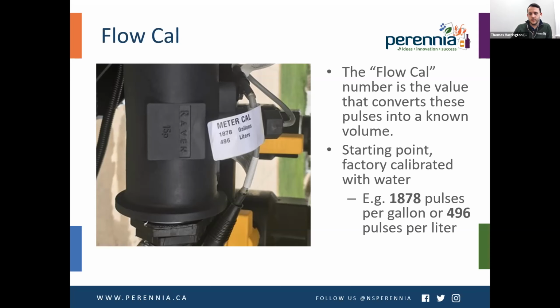What might cause this number to change is if you've got a solution with a slightly different density, or if your flow meter starts to accumulate a little bit of debris, or if it gets maybe worn a little bit. This number might actually need to be fine-tuned and adjusted, and we'll go through that process later.